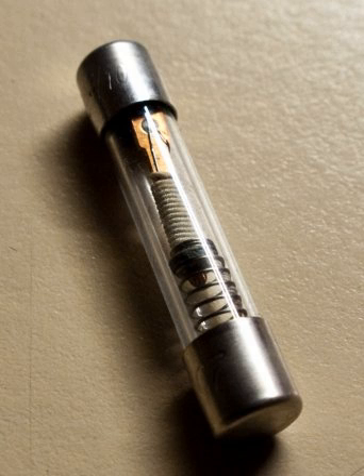A time delay fuse, also known as an anti-surge or slow blow fuse, is designed to allow a current which is above the rated value of the fuse to flow for a short period of time without the fuse blowing. These types of fuse are used on equipment such as motors, which can draw larger than normal currents for up to several seconds while coming up to speed. Manufacturers can provide a plot of current versus time, often plotted on logarithmic scales, to characterize the device and to allow comparison with the characteristics of protective devices upstream and downstream of the fuse.